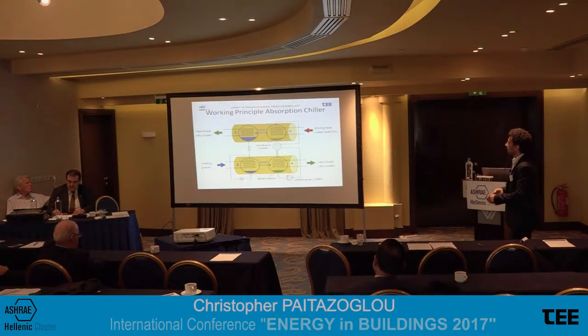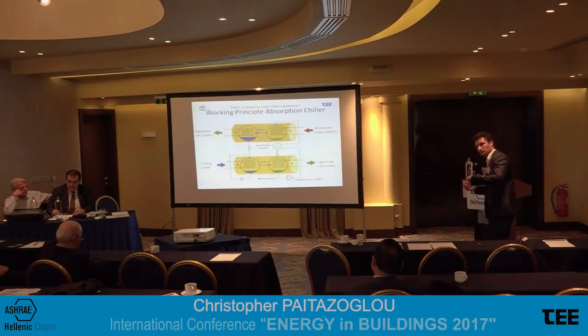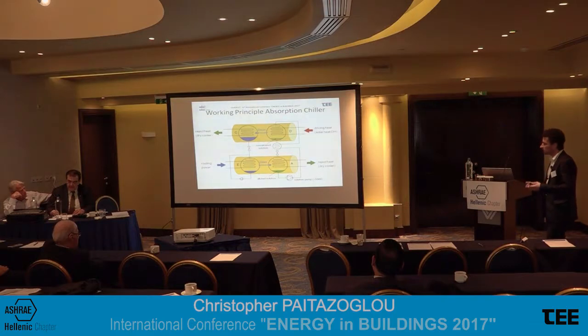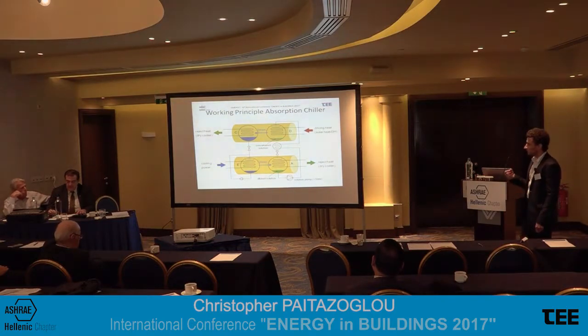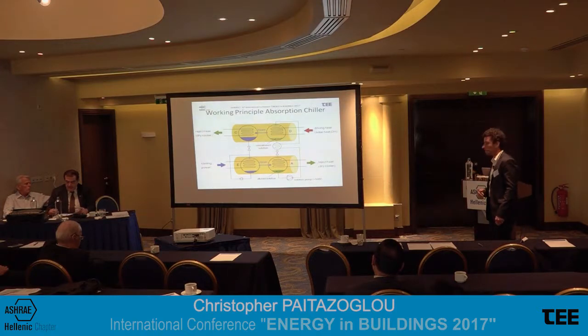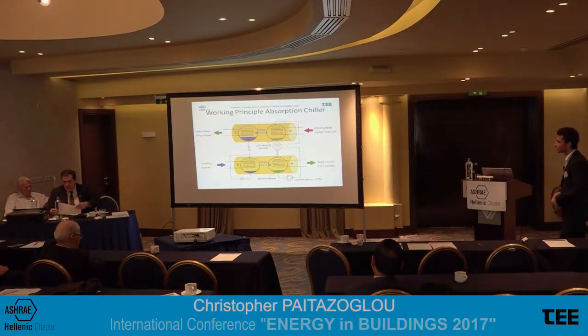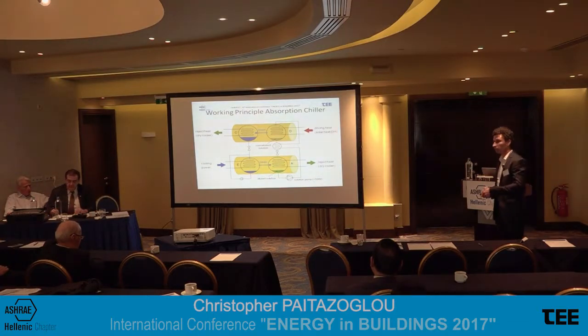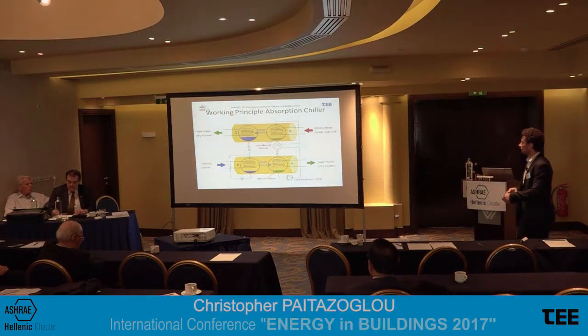On the left side, we have those two heat exchangers, which is basically the same as in a compression chiller. We're using the thermodynamical effect of water that is able to evaporate at a very low pressure. So inside the chiller is almost vacuum, and when we have the external chilled water circuit here at 21 degrees, it can transform the liquid refrigerant into vapor, which then gets into contact in the absorber with the concentrated solution, is diluting it, and this one is pushed up to the desorber where it's been cooked out. And the solution is again concentrated.